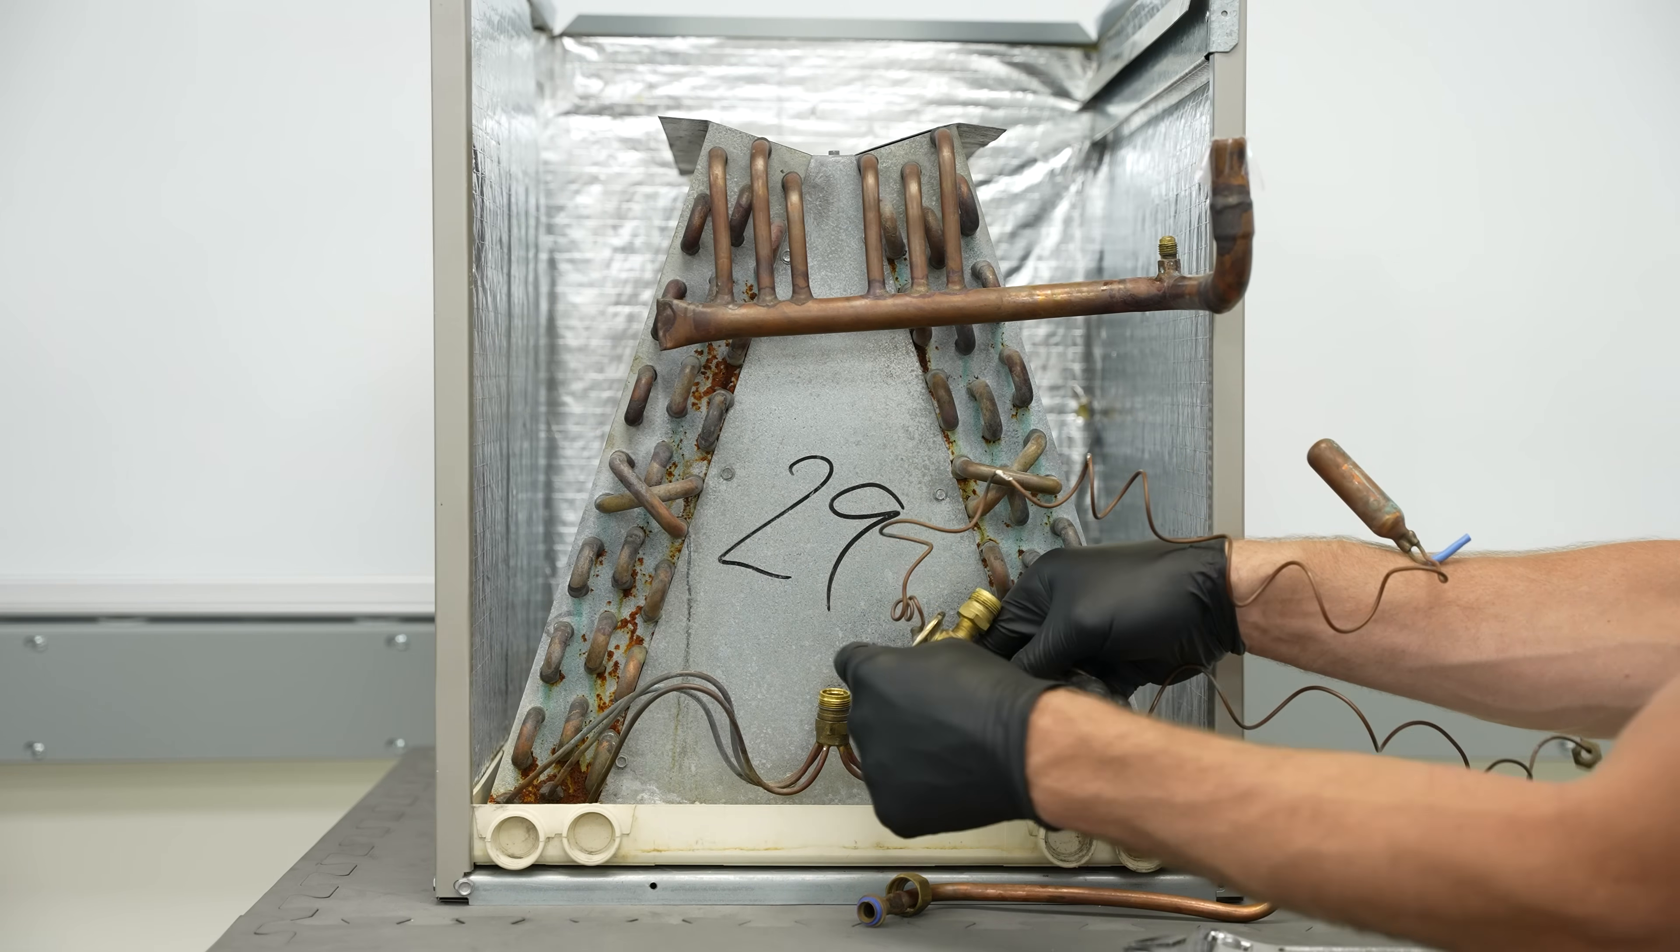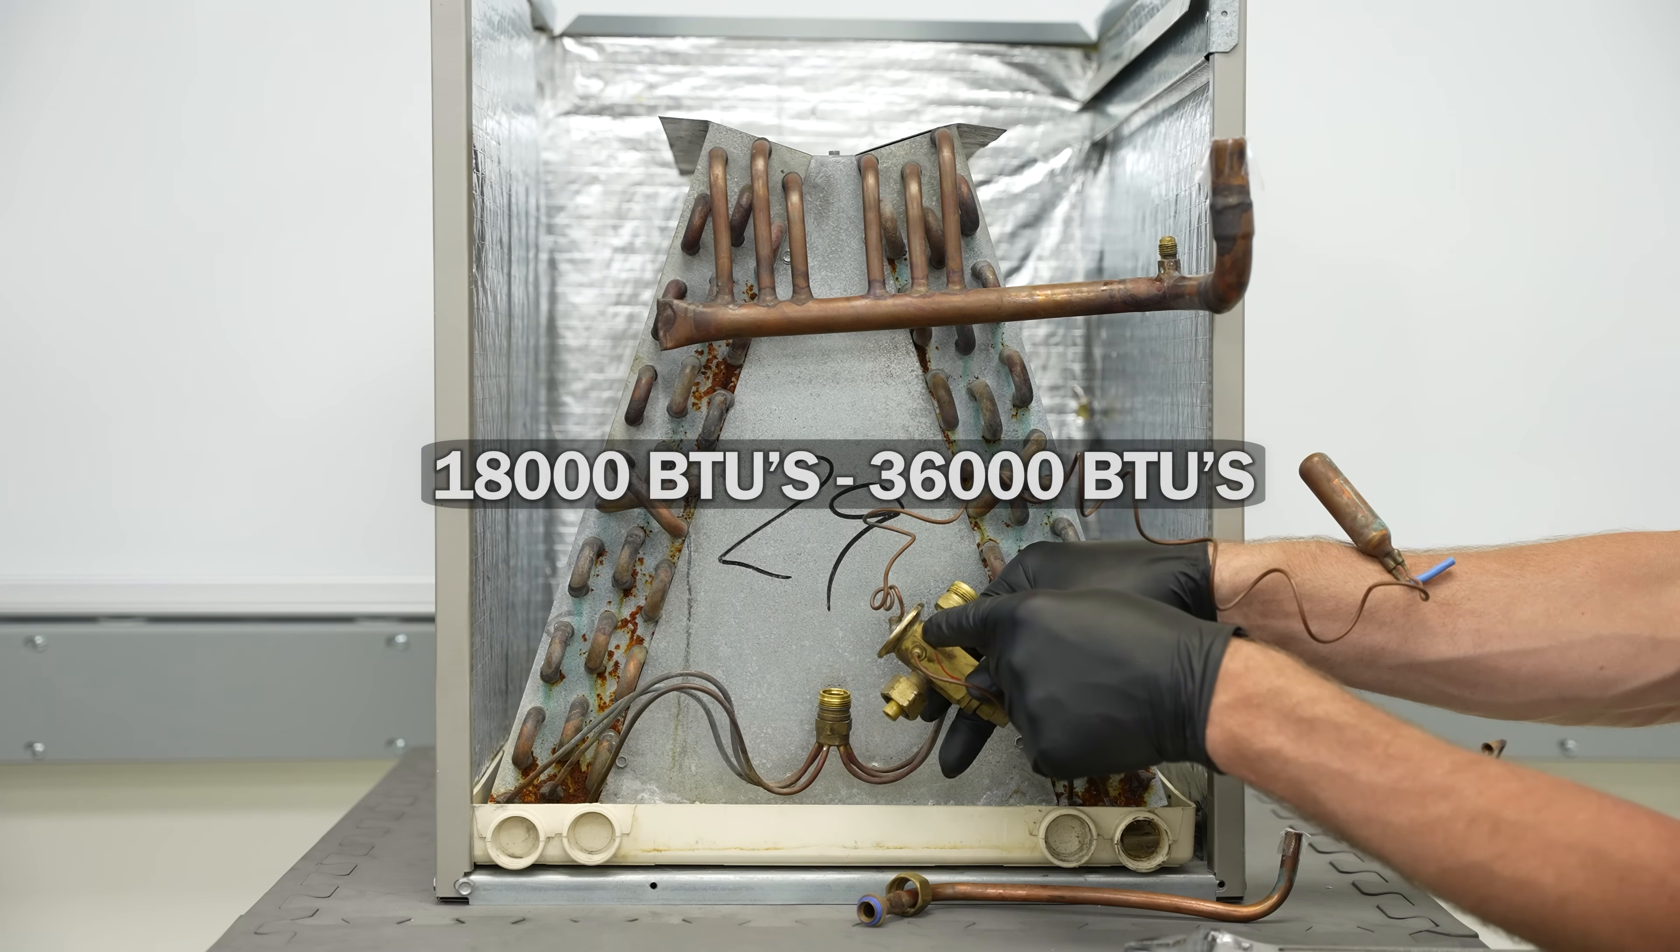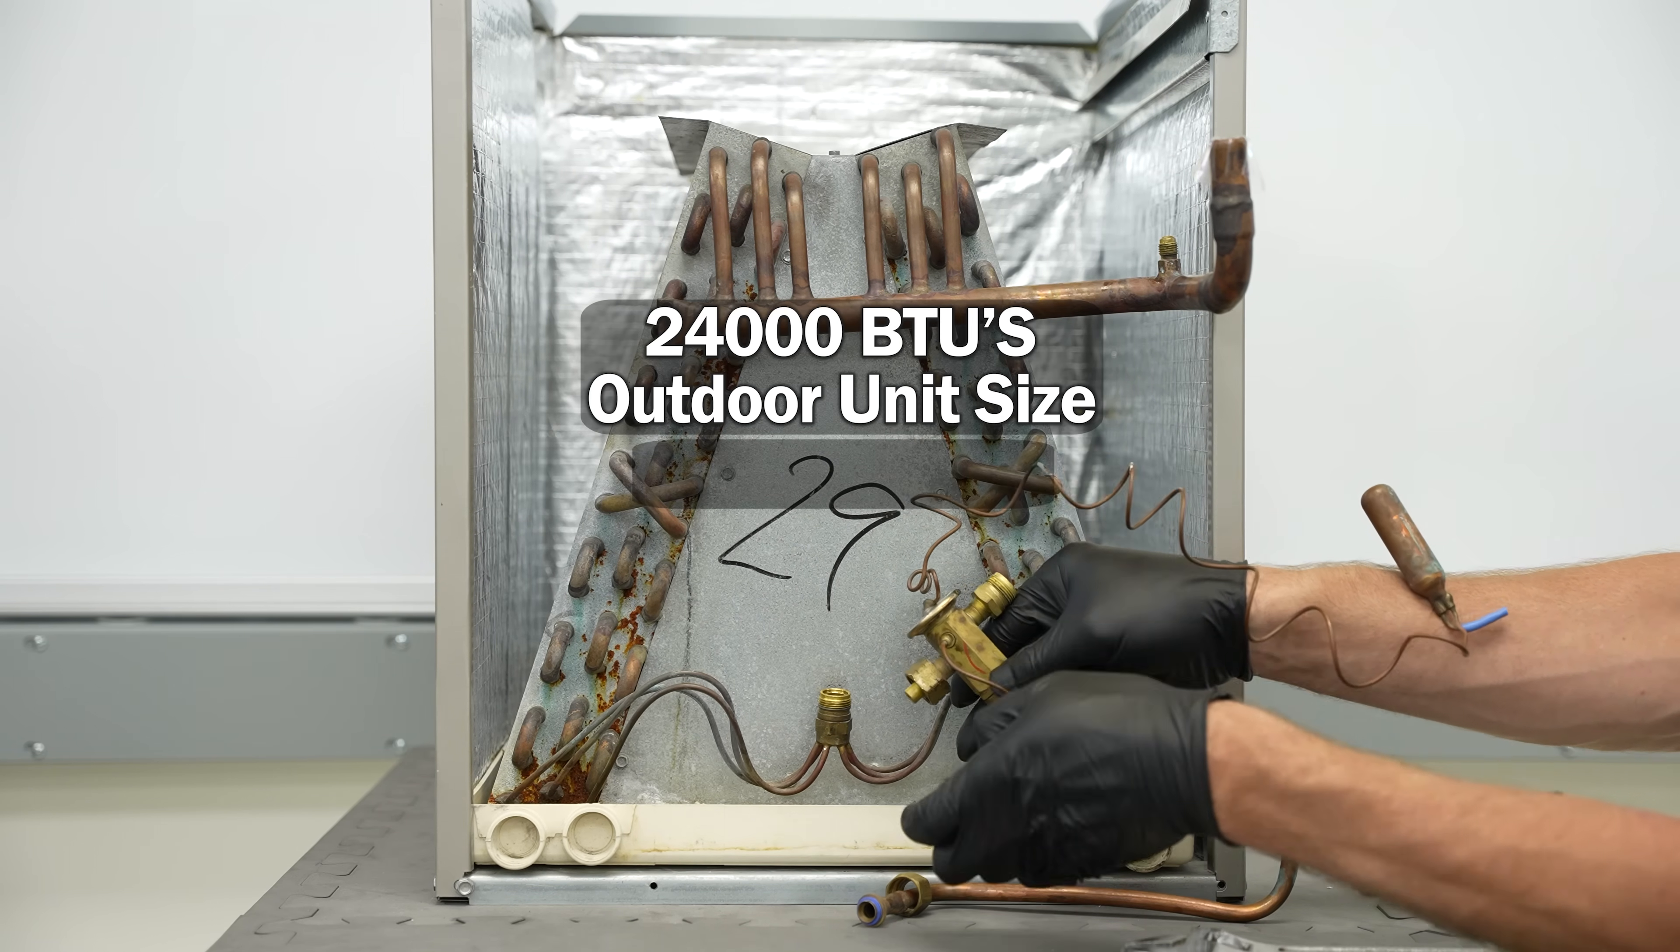Make sure the TXV is rated for the correct refrigerant in the system. At the outdoor unit, it says we have R410A, so this is an R410A TXV. Also make sure that this rating, so this rating is 18,000 to 36,000 BTUs, is covering whatever the BTU size of the outdoor unit is. In this case, it's 24,000 BTUs, so we are good.